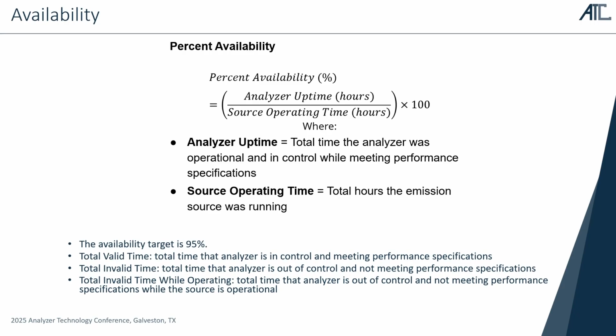So when we're talking about availability, that's one of the most important things when it comes to regulatory compliance for CEMS. The target availability for these systems is 95%. What that basically means is the fraction of analyzer uptime divided by the total source operating time, times 100. So if your incinerator is running or your flare is running and operating, and for the flare example, they should be run 24/7, when you have valid data, that means your availability is 100%.